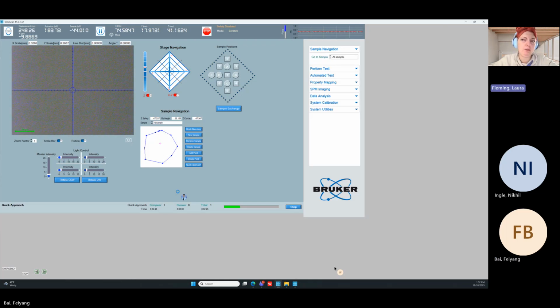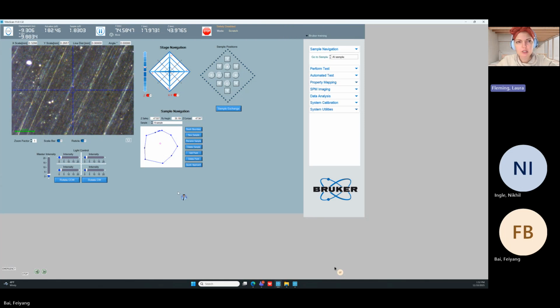Because it did a quick approach, which is completely separate from doing a scratch. If you remember from our discussion regarding the tip to optic calibration, the system needs to have a contact height for the sample, which means the tip has to come into contact with the sample at least once. So let's back up. How does an approach work? You're looking at the sample surface and you say, go do a scratch here. So it lifts the tip up, comes down, and brings it into contact.